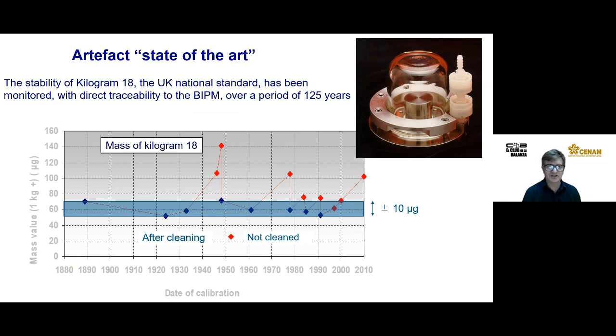Talking about artifact-based definitions, this is the kind of stability you can expect from a primary kilogram, such as the international prototype kilogram or, in this case, the UK national standard, a kilogram of platinum iridium like the IPK. The big issue is that the kilograms get dirty. If they're cleaned, you can get back to a value which is plus or minus approximately 10 micrograms from a reference value. But in between cleanings, the kilograms get dirty at a predictable but not constant rate, so it's very difficult to use as an ultimate primary standard.